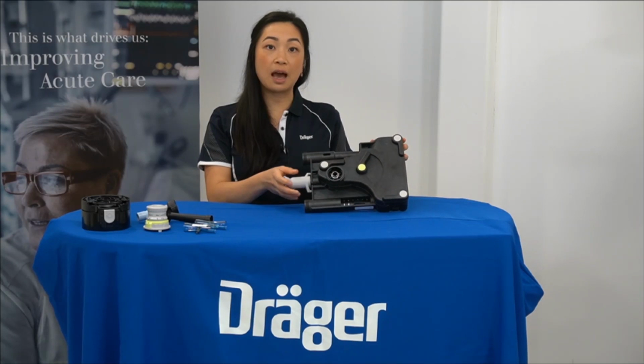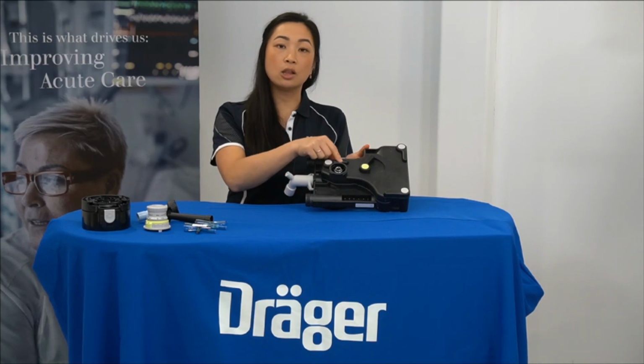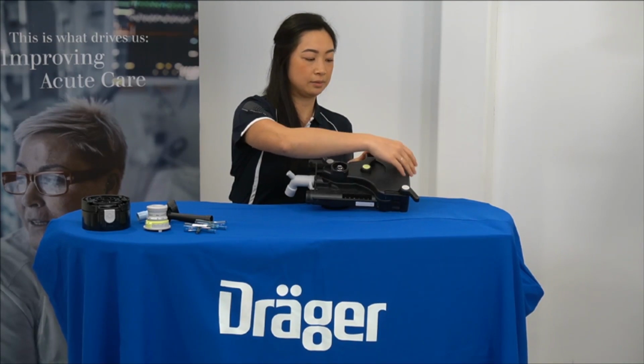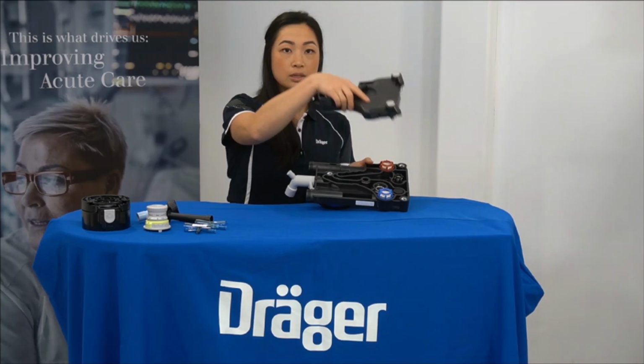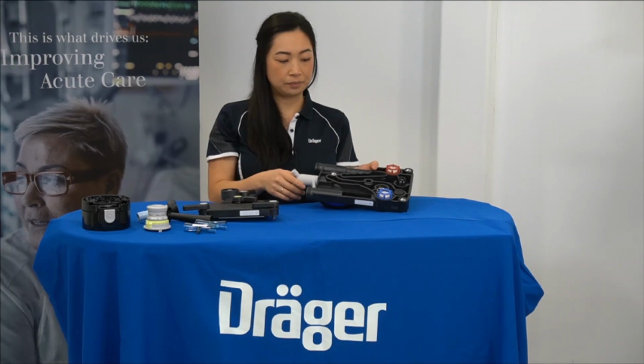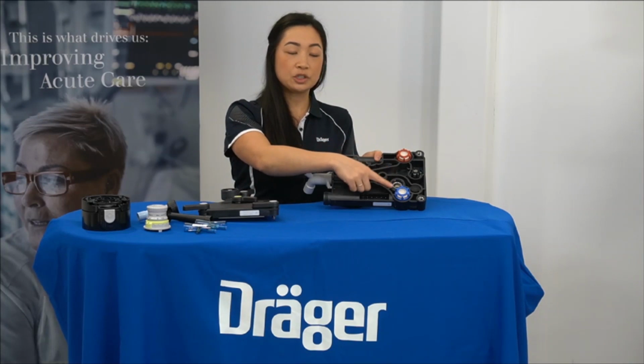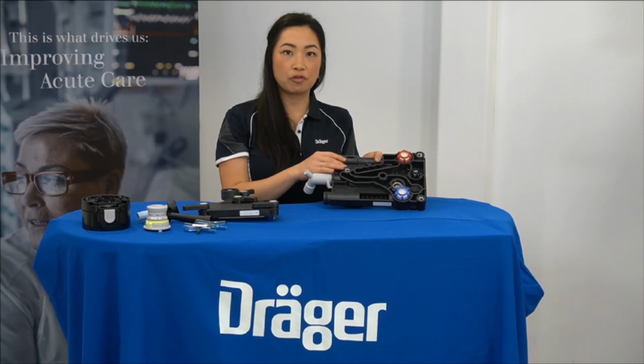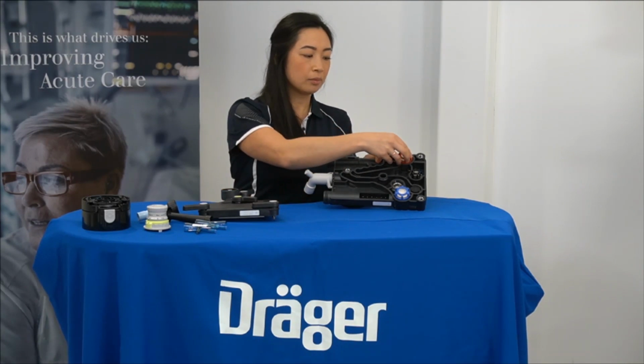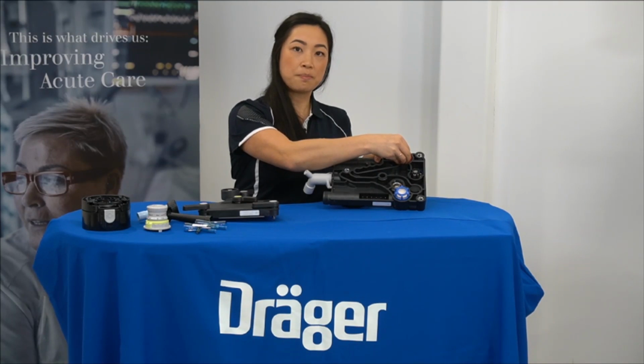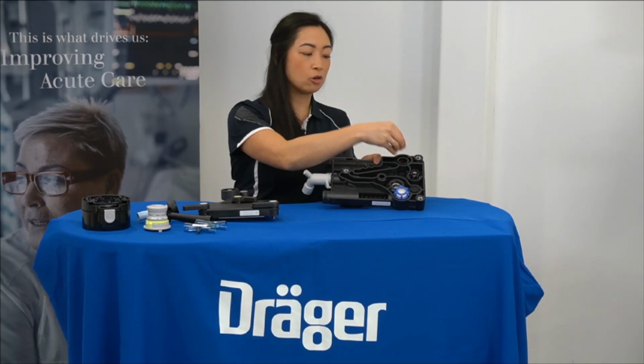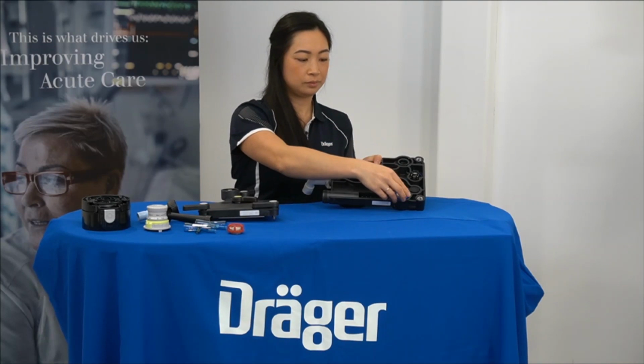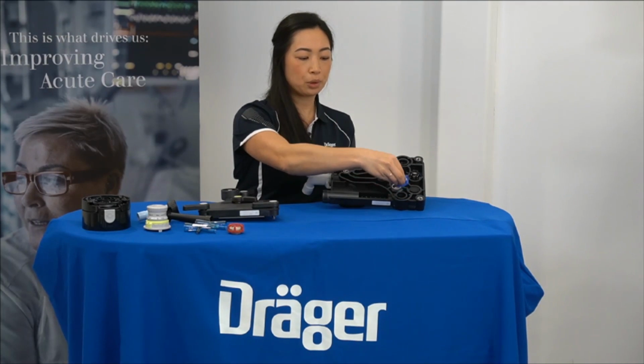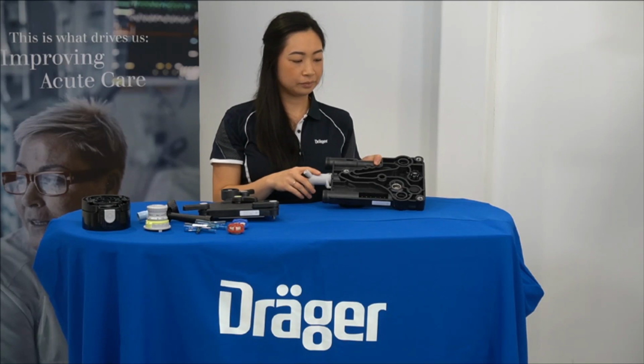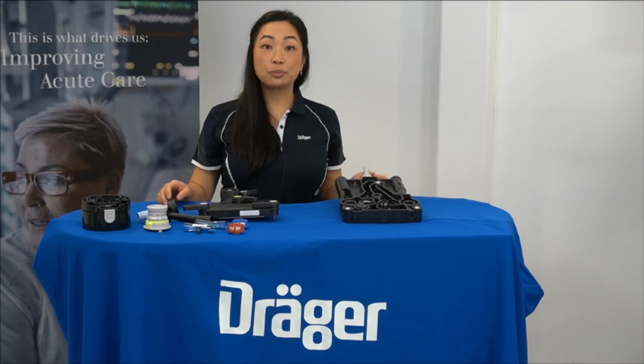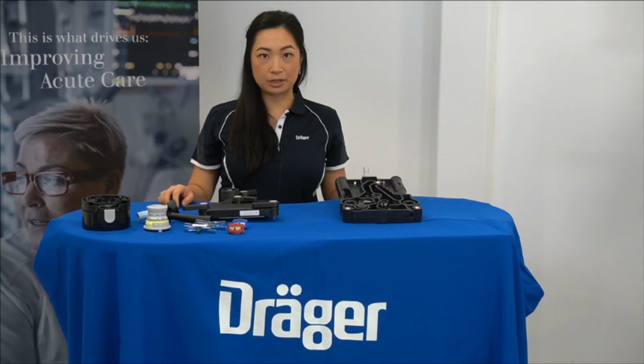Then, to remove the cover of the breathing system, unlock the three grey levers to remove your plate. Next, the inspiratory and expiratory valves can be removed from the base of the breathing block. A forward and backwards wriggling motion will help loosen the valves. And then pulling it out. Now your breathing block is ready to be reprocessed.